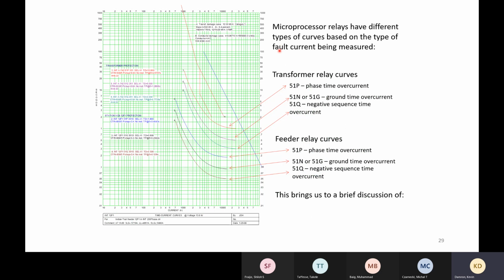So we talked about a lot of advantages of microprocessor relays. There's all kinds of advantages. I don't think I mentioned it yet, but this curve right here is actually my transformer damage curve. So this is what a transformer damage curve looks like. Depending on the class of transformer, it's going to have this knee that comes out of it. The nice thing about microprocessor relays is we get phase elements and ground elements. There's a difference between N and G. N is actually measured, and this depends on the manufacturer. In some manufacturers, the N is for measured ground current, and the G is for calculated ground current. So calculating 3I0, IA plus IB plus IC, gives me 51G.